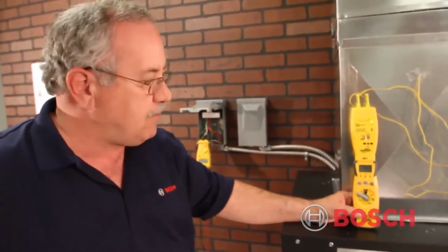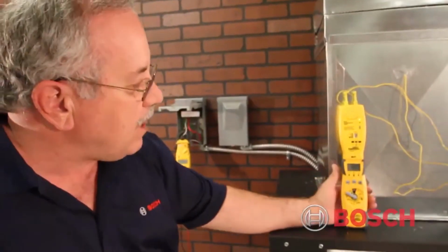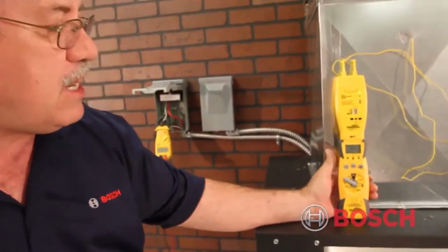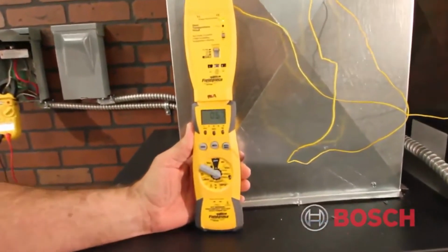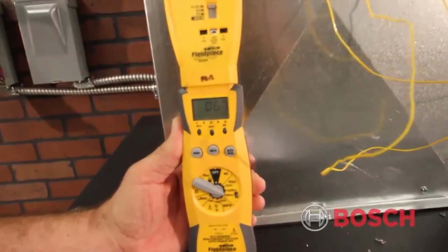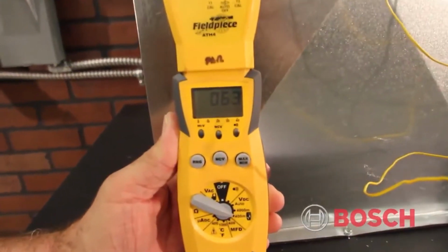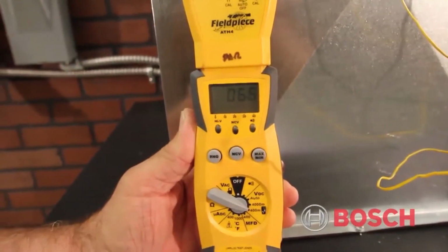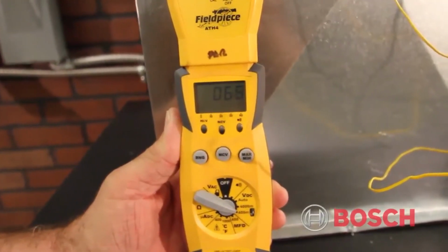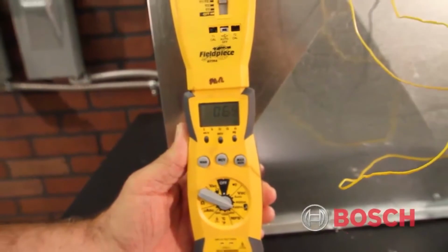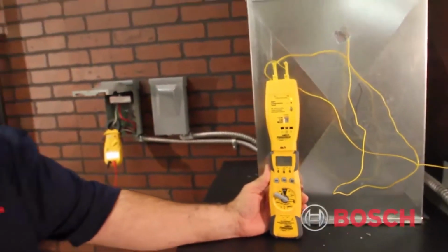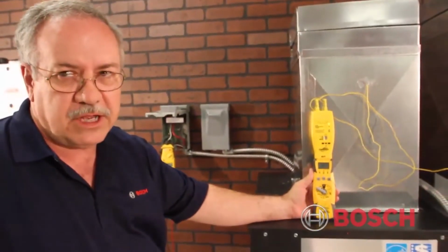Okay, so now that we've finished gathering the data from the disconnect, where we found the operating voltage as well as the amperage of the energized heater, we go back one more time to the delta T and we see that we are somewhere around 6.5 degrees. So let's assume for illustration that we have roughly in the 6.5 degree delta T range. So now we have the three factors that we need to calculate with a formula the operating CFM across this heater.